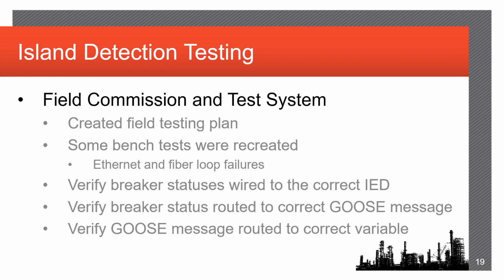So once we bench tested everything, and of course we had to spend a little time troubleshooting our test setup because there's a lot of moving pieces there. We tested all of the various combinations in a matter of hours rather than days or potentially weeks. That allowed us to have a very high degree of confidence that the logic that we built was doing exactly what we intended it to. So whenever we took the logic processor from the bench test scenario to the field, we had extreme confidence that the programming itself was correct.